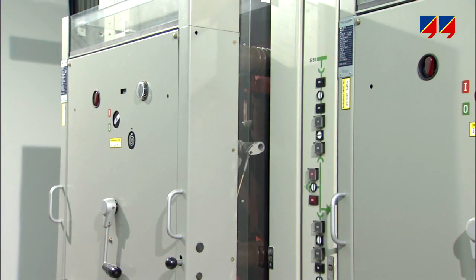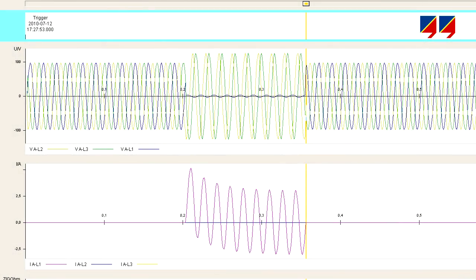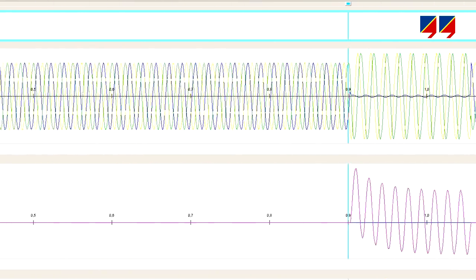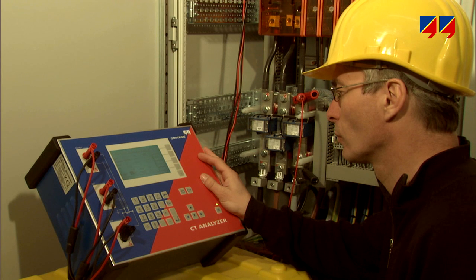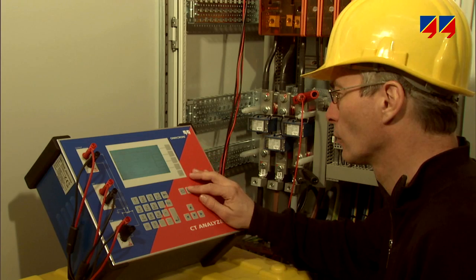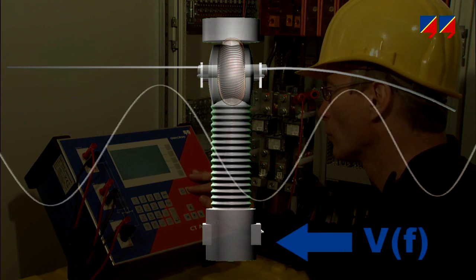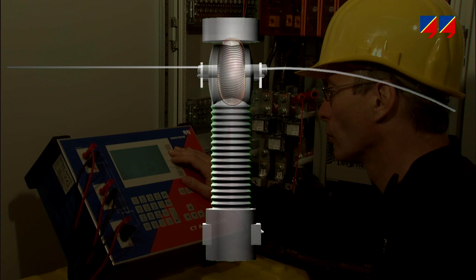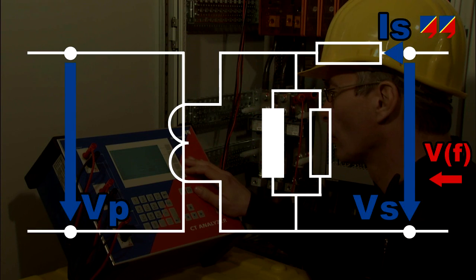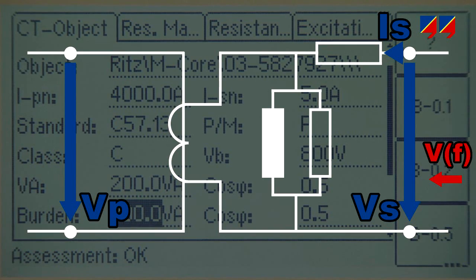Additionally, many of the parameters characterizing a CT's transient behavior — for instance during auto-reclosure cycles, such as secondary time constants or remnants — cannot be determined with classical test benches. CT Analyzer allows the limitations of the various traditional methods to be overcome. It opens the black box through secondary injection with variable frequency and a patented low-voltage, low-frequency method for excitation measurement. It identifies all the parameters of the CT equivalent circuit diagram, and thus accurately determines the CT's behavior for protection and metering applications.